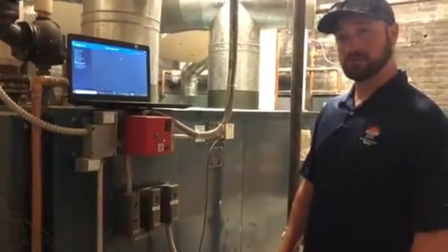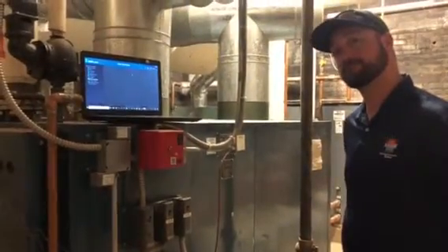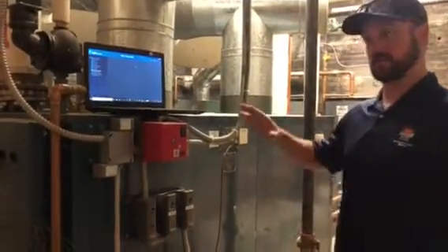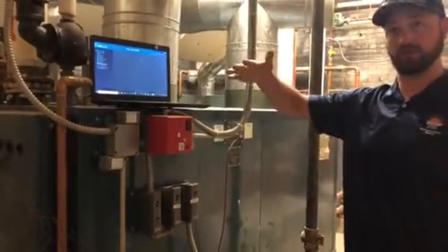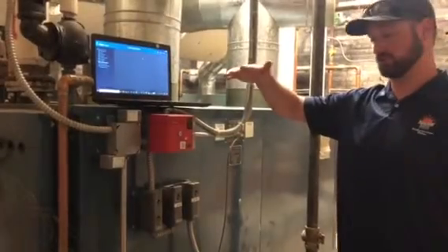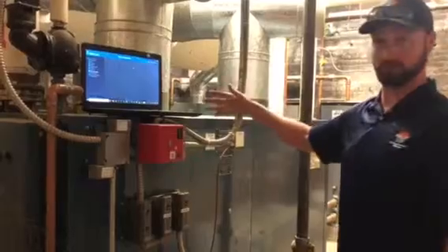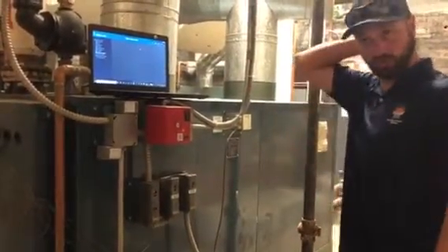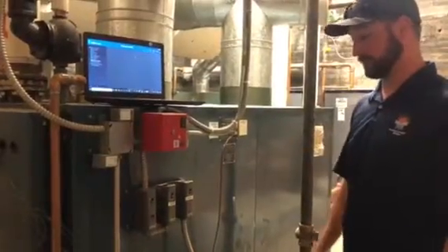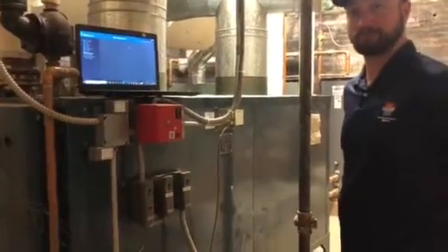Now, as far as the fresh air coming in, you were saying there's 4 different stages on that? Yeah, so there's 2 dampers over there in the corner. With one stage running, one damper will be at 50%. 2 stages running, it'll be at 100%. And then if the other boiler comes on with one stage, then the other one opens the same way. So basically a quarter per boiler.